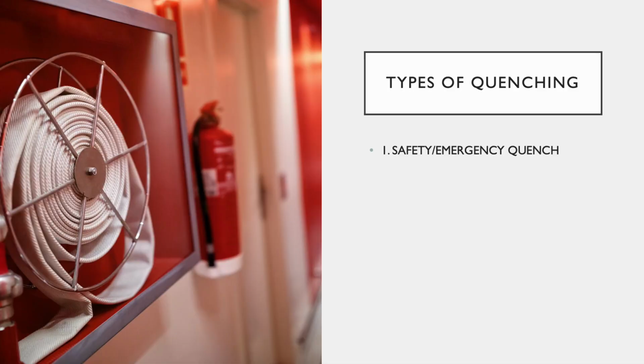Next, let's look at the types of quenching. The first one is a safety or an emergency quench. In some rare cases, clear signage is ignored and metal objects like mop buckets or oxygen tanks, etc., get sucked into the bore of the scanner. These are very difficult to remove while the magnet is at field. And if a patient is somehow pinned inside, an emergency push button, also called the quench button, can be a lifesaver. Therefore, this type of quench is called a safety or an emergency quench.